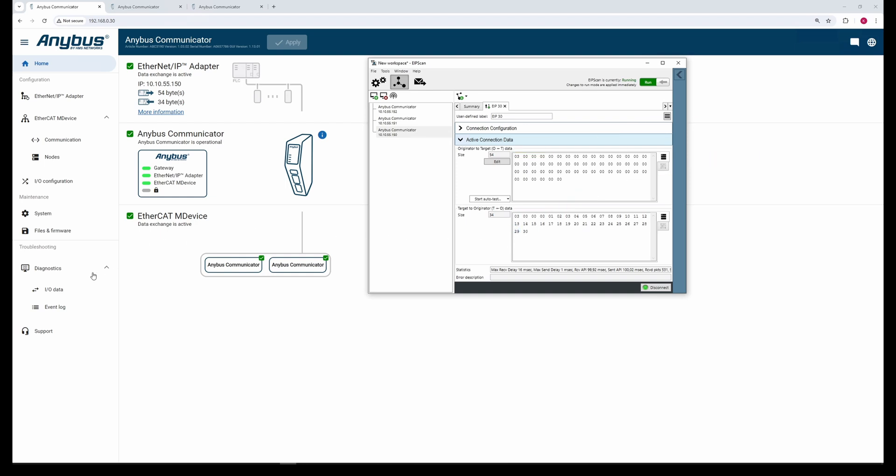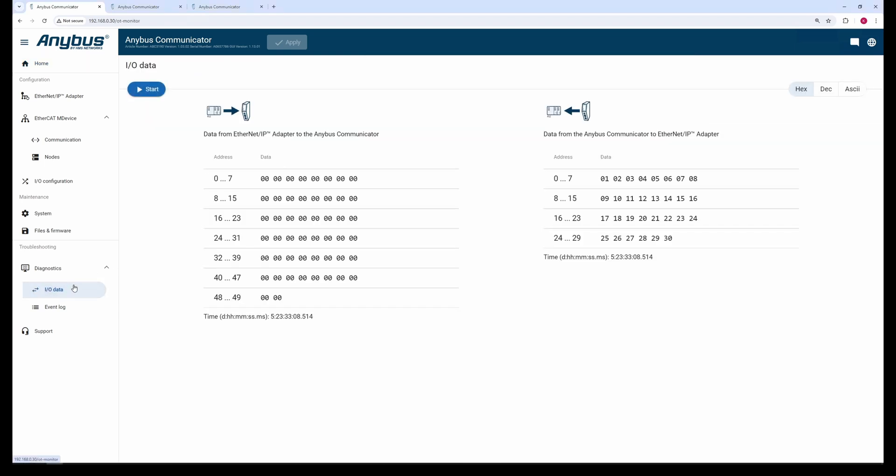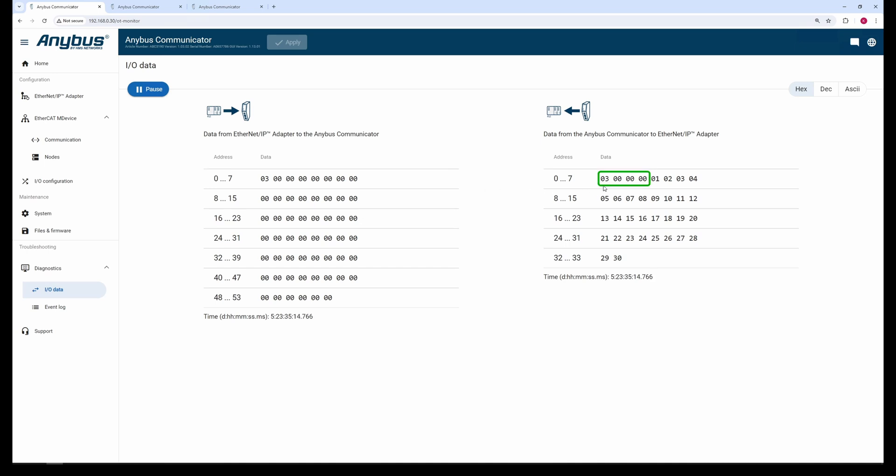In the I/O data monitor, we can now see the increased I/O size of the extra four bytes that make up the Data Exchange control and Live List. In the left column, we can see the Data Exchange control with a value of three, binary node one and two, in the first four bytes. To the right, we see the Live List in the first four bytes, followed by the input data from the sub-devices.